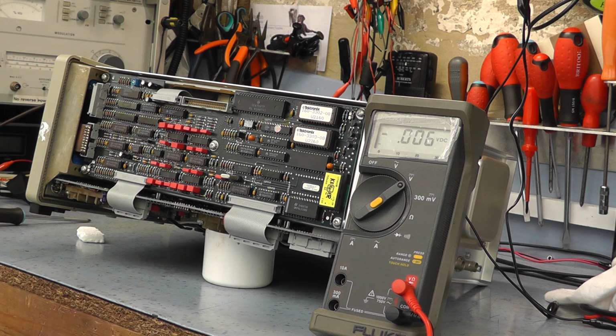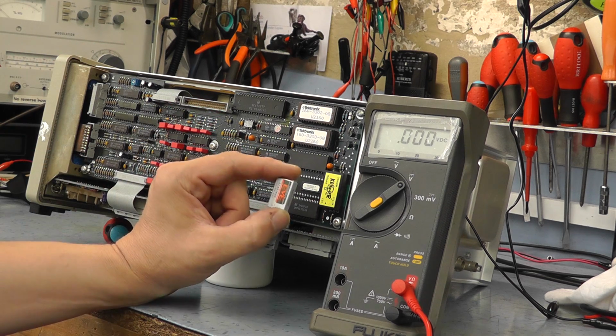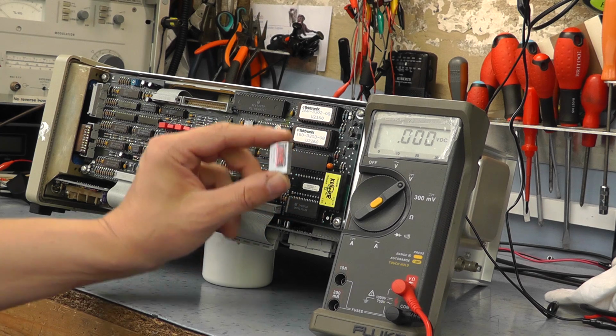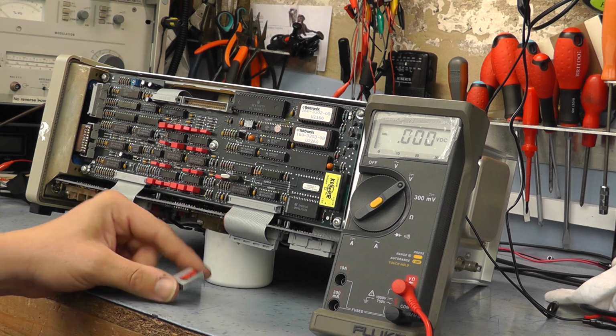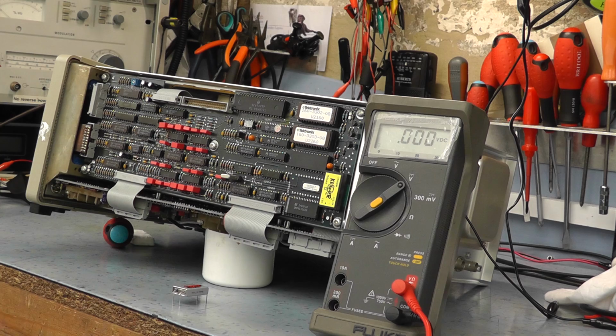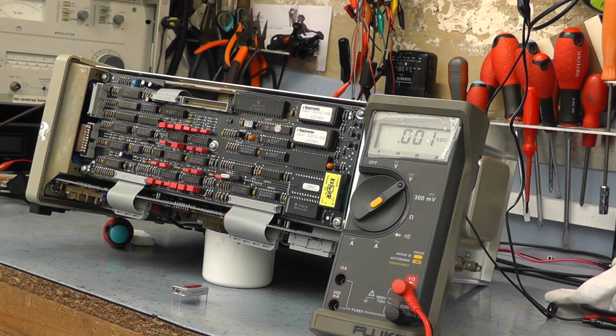I need to change this battery, and I've got another battery, the equivalent battery, and it's pretty hard to see here, but this battery is actually quite a little bit smaller than the existing battery that came on the scope board. The other thing apparently is, what you don't really want to do is disconnect the battery for any length of time, because if there are any settings in there that are valid, you will lose them. Probably not a bad idea, because I think it probably needs a total recalibration anyway.